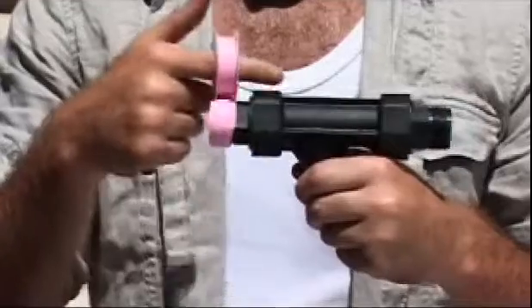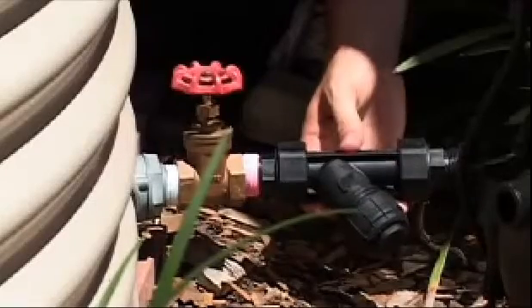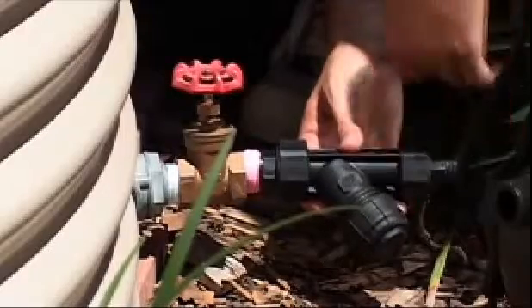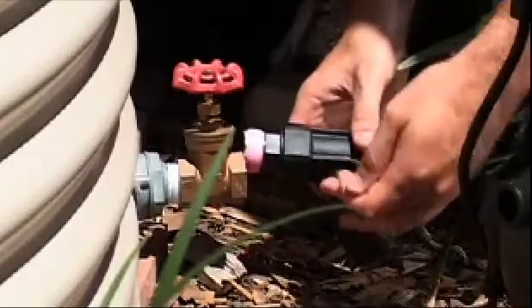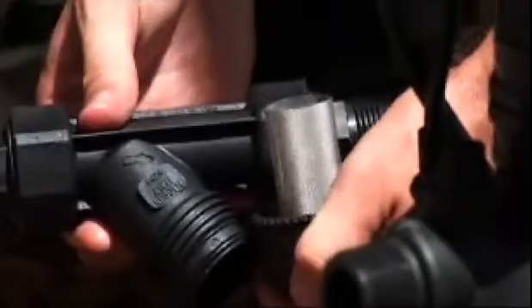Firstly, wrap some plumber's tape clockwise around the male thread of the strainer — around five times should do it. Then attach it to the gate valve using your wrench. I'm using a Y strainer on this job. As you can see it's shaped like a letter Y and it has a screen inside. Make sure the strainer is facing down so that when the water stops flowing, debris will naturally sink to the bottom. From time to time you will need to empty the strainer and see what you've caught.